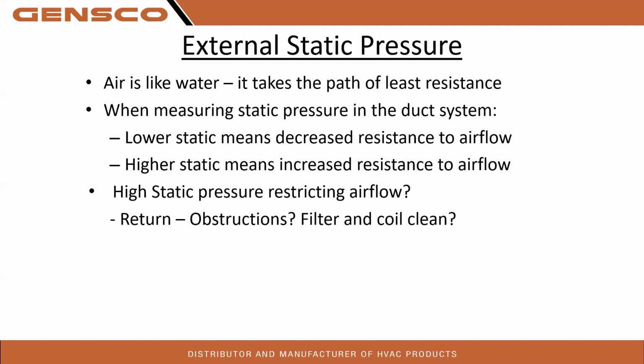I always heard my contractors say, don't worry, we'll change the filter. Well, yeah, you show up to do a startup and that filter is so caked with sheetrock dust. It's just horrible, right? Yeah, that's a great point. If the new construction put the filter at the return air opening to protect the ductwork and the unit. And I know in some cases in commercial TIs, tenant improvements, we were having to cover the ductwork. So to eliminate any kind of that, but again, look for your return obstructions.